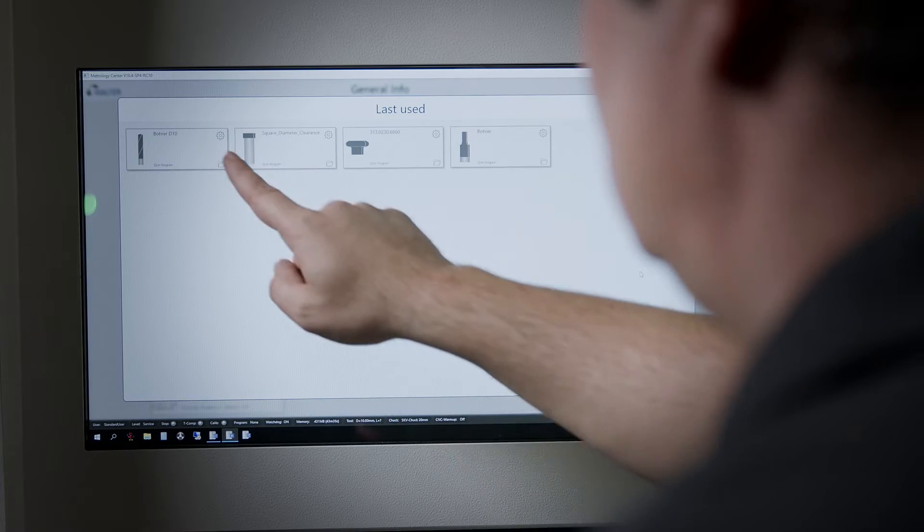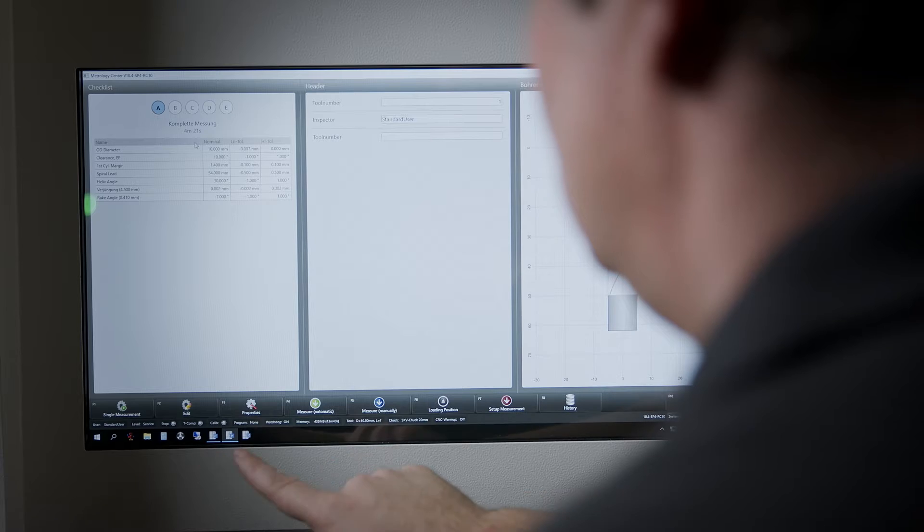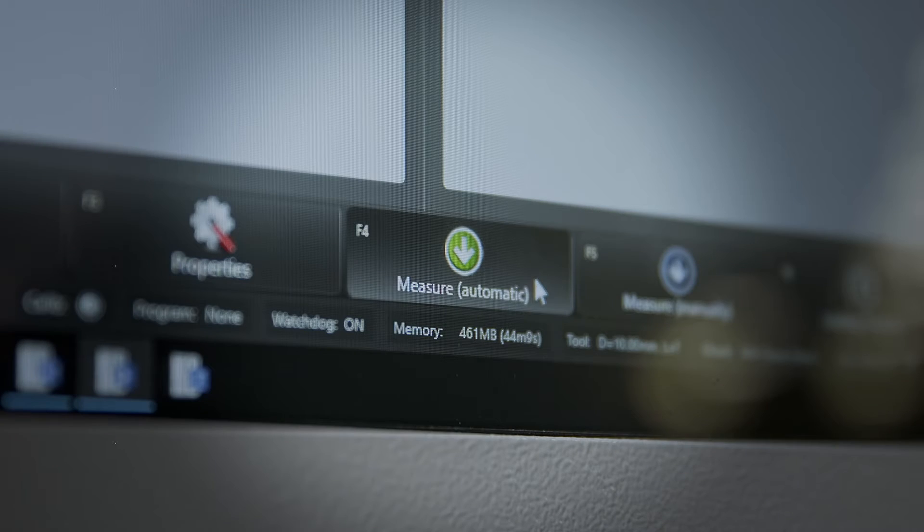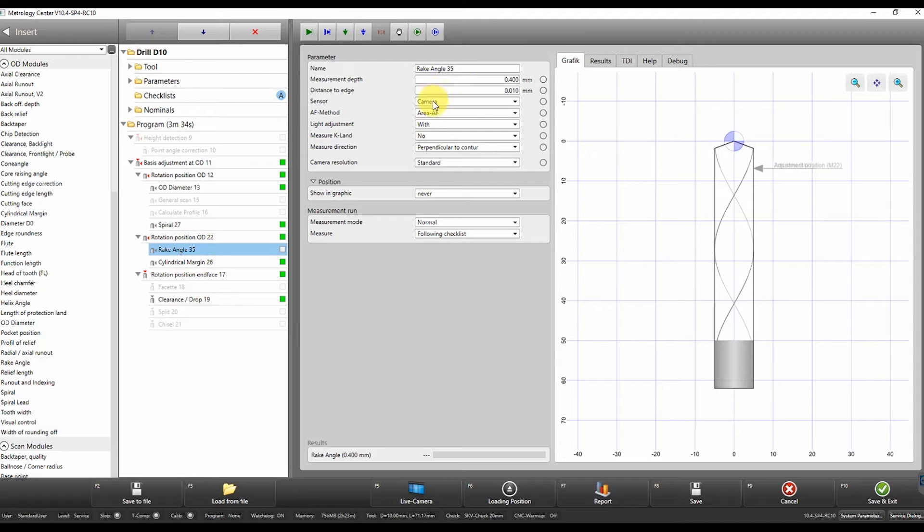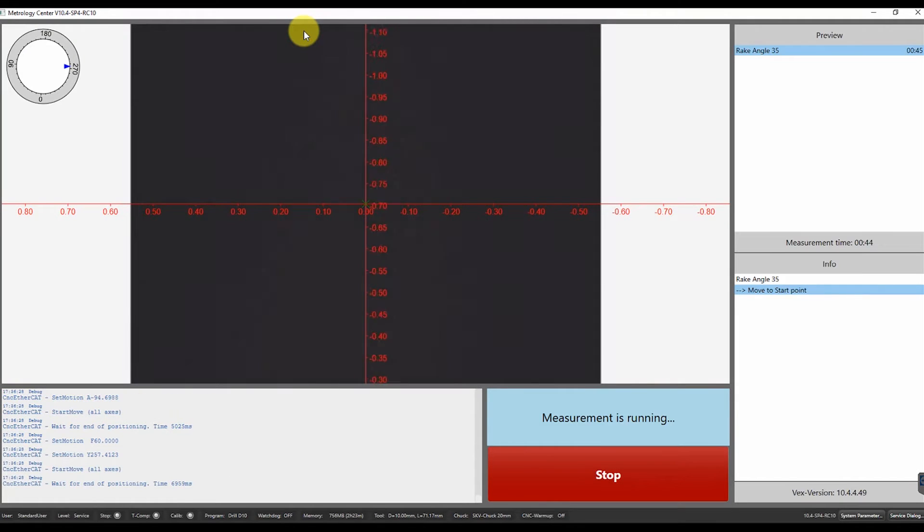Both probes are activated in the settings of the various measuring modules on our CNC measuring machine. A key factor for deciding which measurement technology should be used for which tool is the surface quality and the reflection behavior of the tool surfaces.